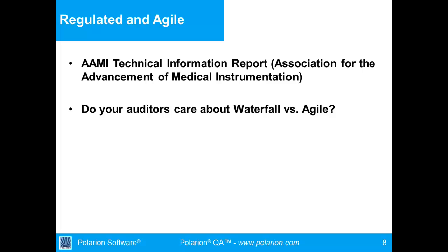There's no real conflict between using agile development practices and testing methods and working in a regulated environment, particularly the FDA. If people get a chance, they should try to Google a thing called the Guidance on the Use of Agile Practices in the Development of Medical Software that AAMI is putting together. It has some really interesting recommendations that are beginning to come out of it. It's still in draft form, so you might have to go find the people on the committee and figure out who you would know between them. There are some public presentations that some of the committee members have given about some of the results of what the committee is putting together.